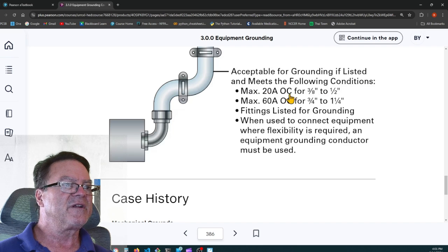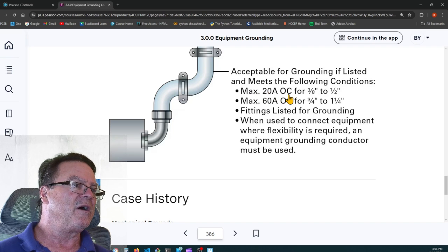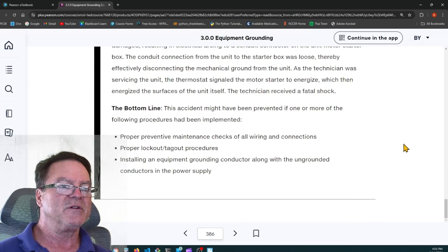and it's acceptable for grounding if listed and meets the following conditions: the maximum 20 amp circuit overcurrent protection for 3/8 to 1/2 inch, maximum 60 amp for 3/4 to 1.25 inches. Fittings are listed for grounding, and when used to connect equipment where flexibility is required, an equipment grounding conductor must be used.